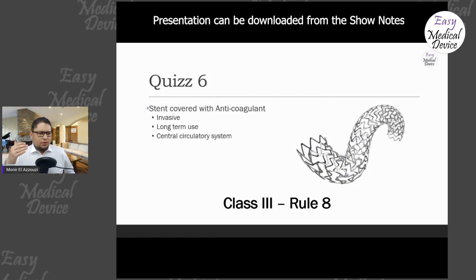So you see that with one device, you can have many rules applicable, but you have, as a regulatory person, really to define which one will work. So here we can say rule 8, we can say rule 14. I don't know if there is maybe another one. I don't know if the one with substances will apply, because for the one with substances we now really have to be careful. Rule 21 is one that will really be used, but no, this one is not applicable because it is mainly for products that are skin touch, absorbed by the human body, or applied on the skin, etc. So it's not applicable. But you see that it's something you really have to interpret. Get all the functions of your device, the intended purpose of your device, then go through all the rules. As I've said, don't miss one, just go through all the rules one by one and pick the ones that are really applicable. But I have here a lot of good answers, so thank you for that.